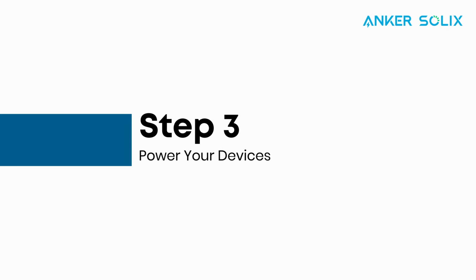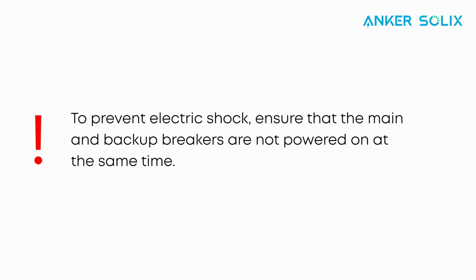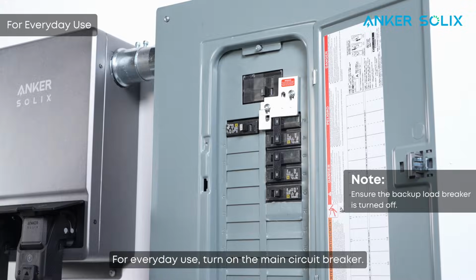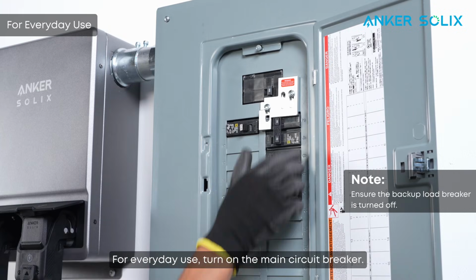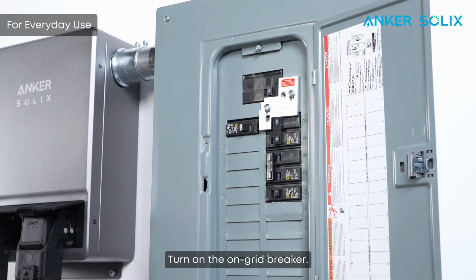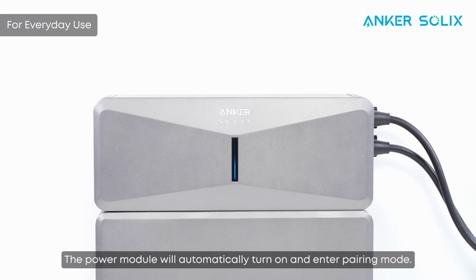Next, here's how you power your devices. To prevent electric shock, ensure that the main and backup breakers are not powered on at the same time. For everyday use, turn on the main circuit breaker. Turn on the on-grid breaker. The power module will automatically turn on and enter pairing mode.